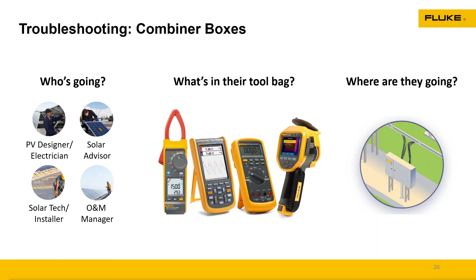This is also a good way to check if you do have ground faults, because you can pull your fuses and take a digital multimeter and go between your hot and your ground, and your DC positive and your DC negative, and see if you have an equal amount of voltage there or it'll drop out. There was a company in Georgia that reached out, and that's how they were doing it. They were actually taking a DMM, pulling the fuses, and then going between positive and negative and making sure they had an equal amount of voltage there. If they didn't have an equal amount of voltage, they knew they had a ground fault, and they could start doing that investigation back on the panels.